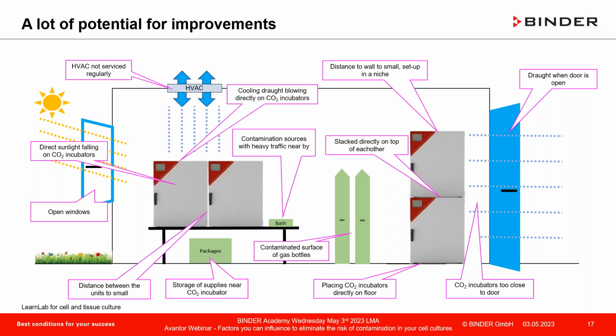And not quite sure if you were aware of that, but please do not position, regardless of brand, regardless of model, CO2 incubators below a HVAC. Because on the one hand side, sunlight heats up the outer housing, and the HVAC air draft coming from directly above cools that surface, and then you have condensation inside of the chamber because you're cooling the outer surface, and that will eventually creep inside, cause condensation, and at 37 degrees C, it's dark, it's humid in there for your cell cultures, especially when you're working with Petri dishes.